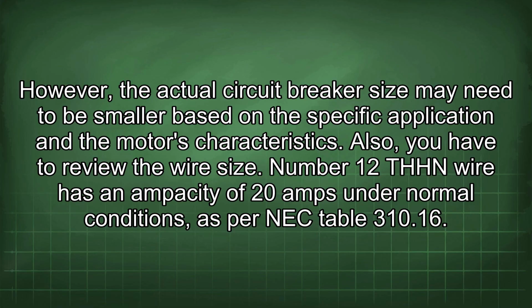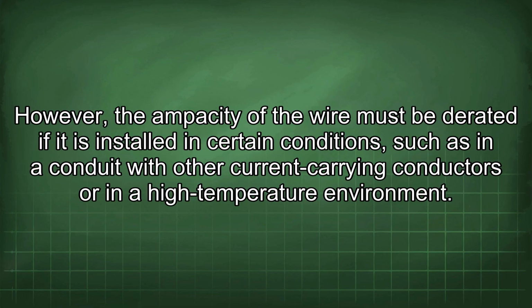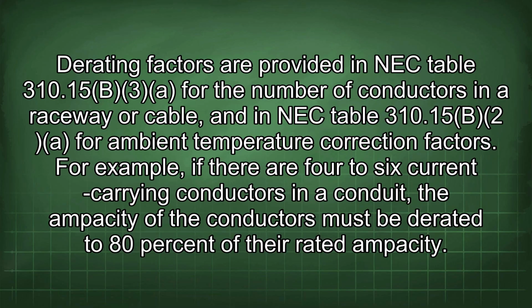Number 12 THHN wire has an ampacity of 20 amps under normal conditions, as per NEC table 310.16. However, the ampacity of the wire must be derated if it is installed in certain conditions, such as in a conduit with other current-carrying conductors or in a high-temperature environment. Derating factors are provided in NEC table 310.15(B)(3) for the number of conductors in a raceway or cable, and in NEC table 310.15(B)(2) for ambient temperature correction factors.